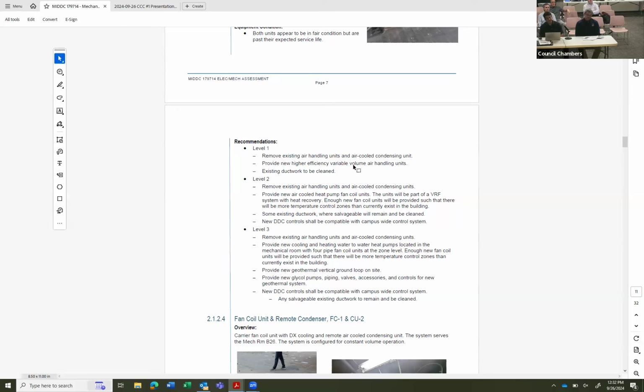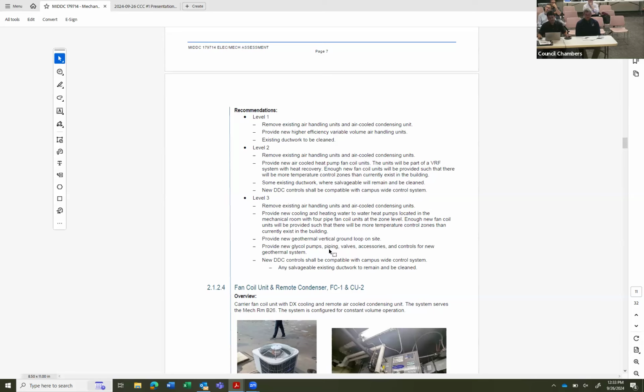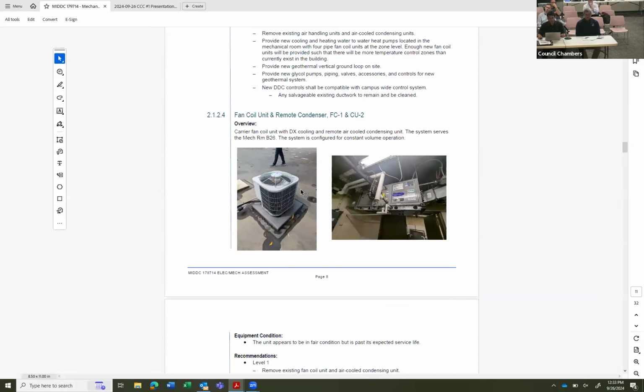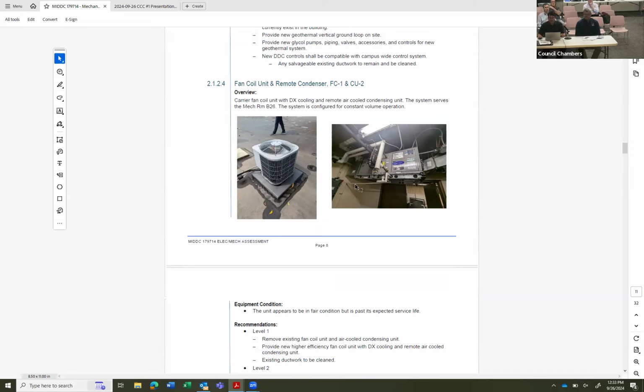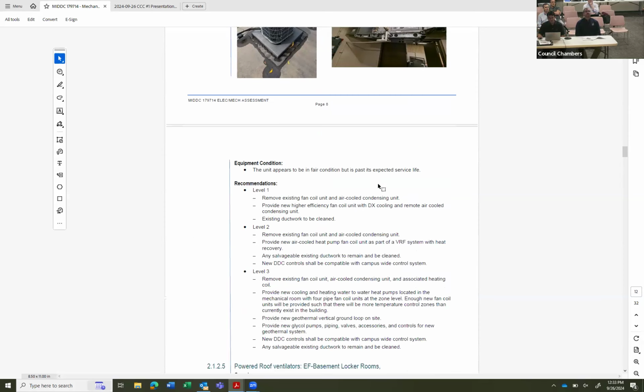And similarly with level 3, with the geothermal system, we would be removing the air handlers and replacing with heat pumps in the basement, as well as providing new glycol pumps that would be pumping to the geothermal loop, and all these zone level fan coils, which would be similar to the level 2 option. So the air handler in the basement would go away, be replaced with the refrigerant or the geothermal system. And similar with the fan coil unit, same thing, basically a lot of the same concepts apply. It's just a smaller zone level unit. Single zone, I should say.